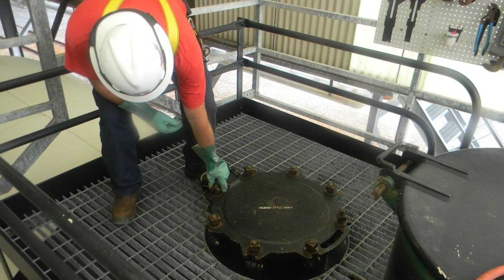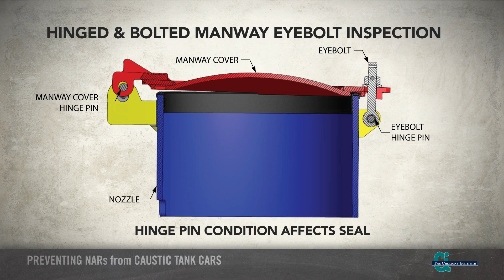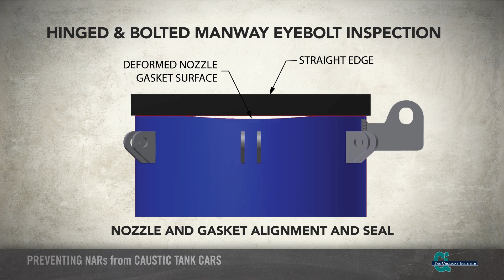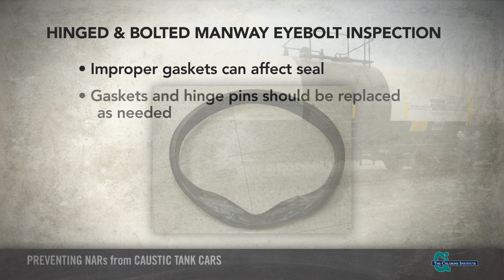Ensure that the manway cover is in alignment with the manway nozzle and the gasket is aligned and sealed properly. Eye bolts can be placed into position without tightening to help identify alignment issues. If the manway cover does not appear to be aligned, inspect the manway hinge pin for damage and the hinged manway nozzle for roundness. A bent or damaged hinge pin or a flat out-of-round nozzle can prevent the manway from aligning and sealing properly. Sealing may also be impacted by rolling, pinching, or misalignment of the gasket.